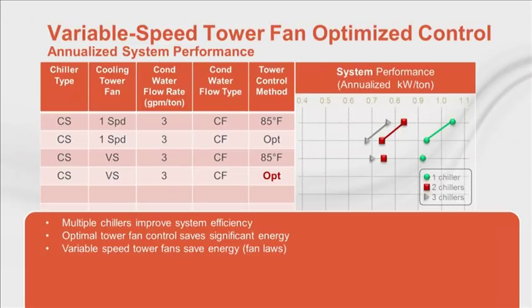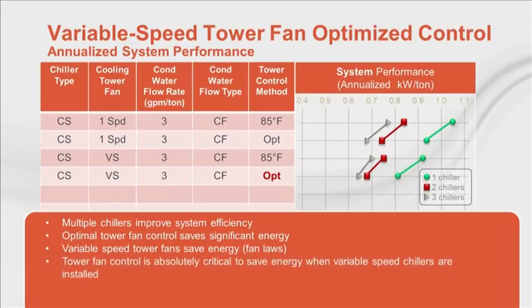Now we'll take the same system and optimize the cooling tower fan control. Again, there is a significant savings simply by dynamically finding the optimal tower set point. Now some people might stop here, but there still is some low-hanging fruit to be picked.